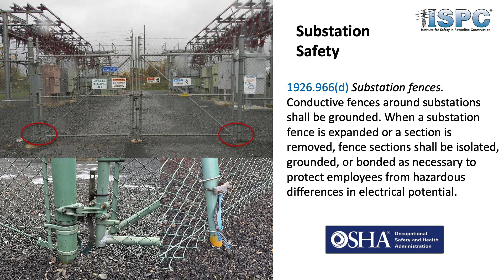You can see in the top picture a substation gate. A lot of people, and I know this because I worked for a utility and had people work for me as a supervisor, I've watched countless people pull up to a substation, stick the key in the lock, unlock it, throw the gate open, and go in the sub. Well, if those fence grounds, or the bond between the substation fence and the gate shown in the bottom left picture, are compromised, opening that gate creates a difference of potential between those two fence panels. At our smaller distribution subs, it's probably not that big of a concern, but you still have to be aware of it. As you get into higher voltage transmission stations, where induced voltage is a much bigger concern, this could become a tremendous hazard you need to recognize.